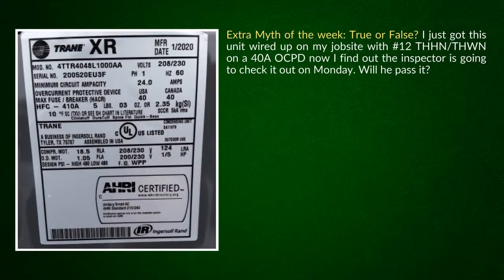Well, when I go through this, one of the things I think everybody will appreciate is, there's been this argument. They've tried to argue with me on motors, because I establish a minimum, next, and maximum size when I'm sizing my overcurrent protection device. And they say there's no minimum. I said, no, it's a starting point. You can go below that. I said, go look at some of the AC unit nameplates. Some of them have on there minimum breaker size and maximum.